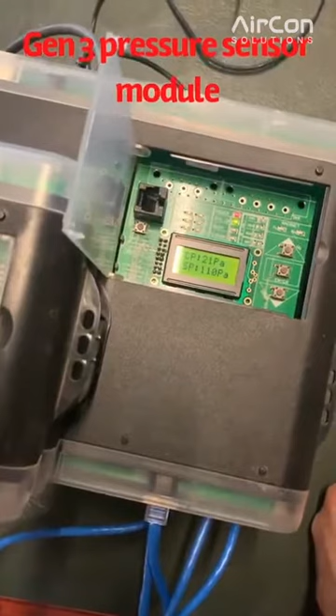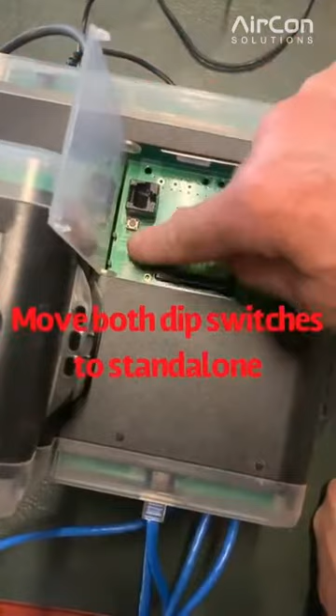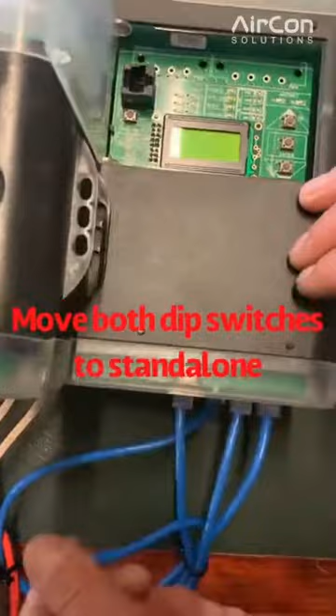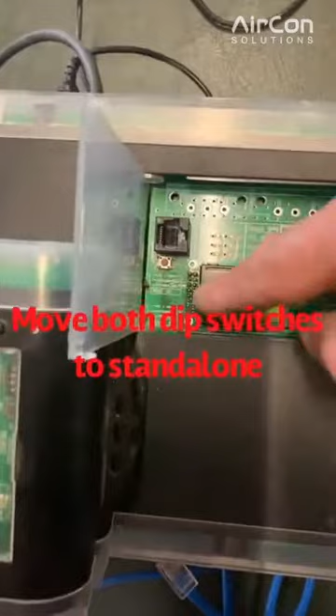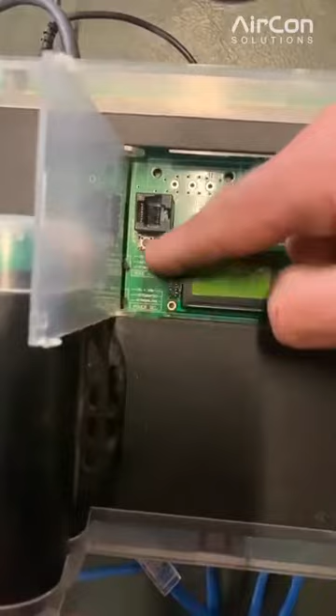So what we're going to do is show you how to recalibrate it. At the moment, they've got two sets of dip switches here, both set to integrated. We need to pull out the blue cable and move these to standalone. So we've got DS plus VAV, integrated, and standalone as the three options.